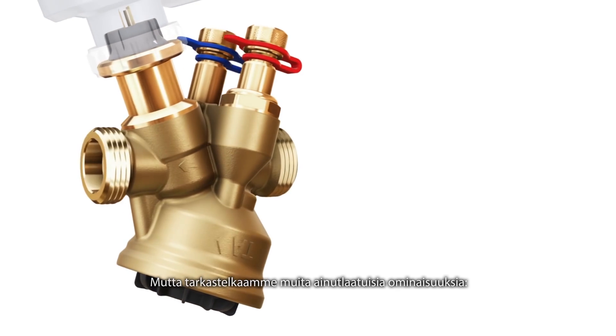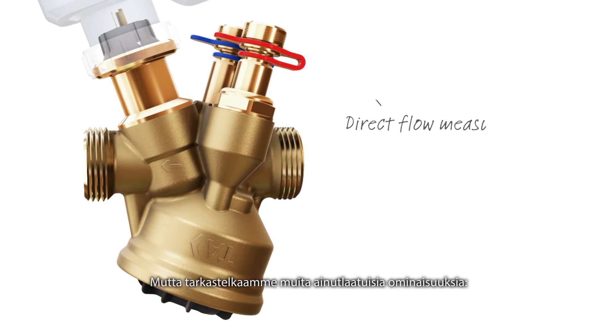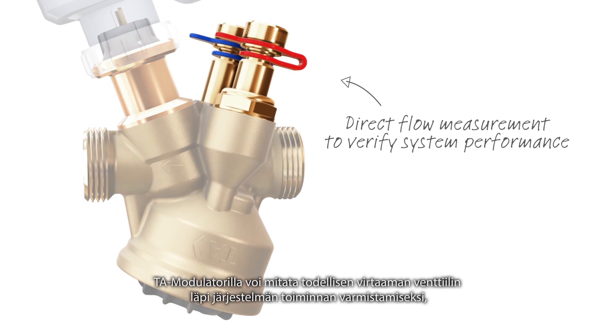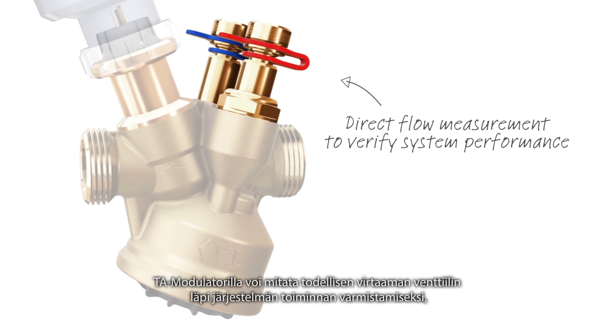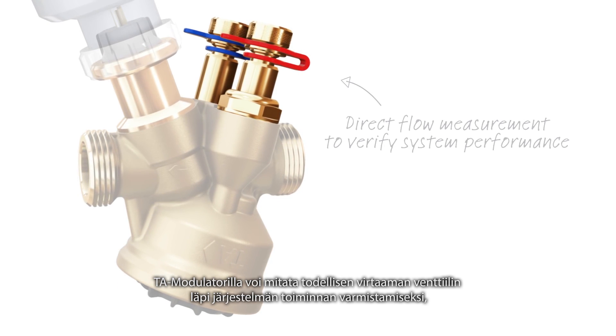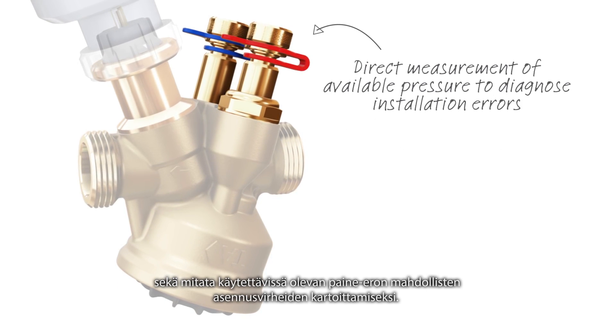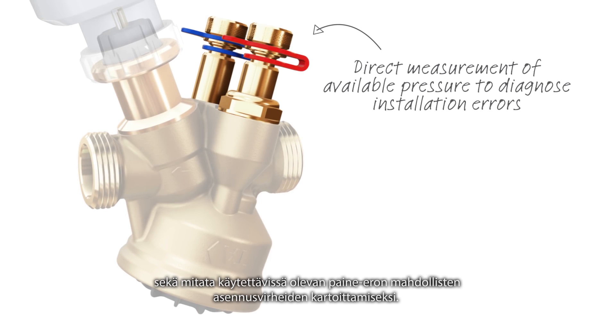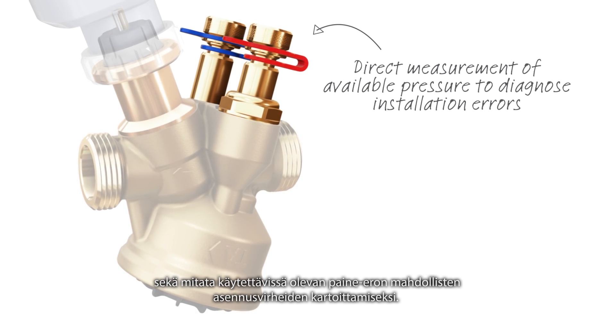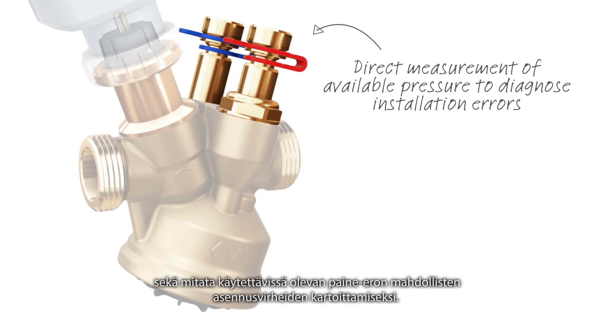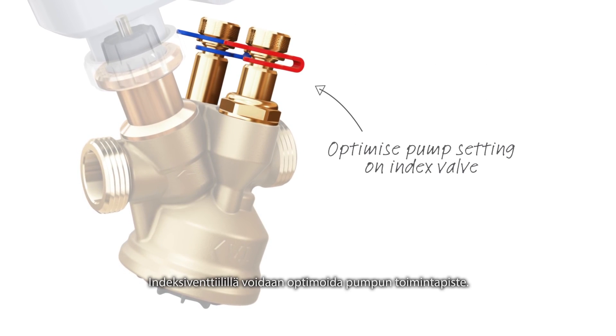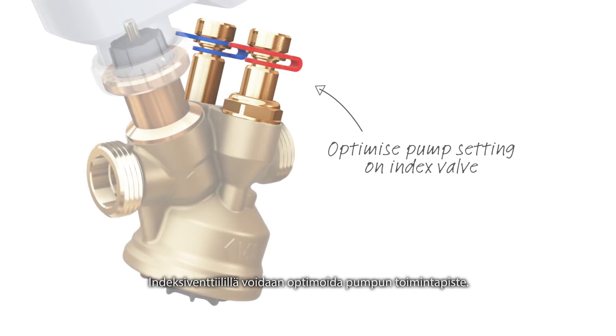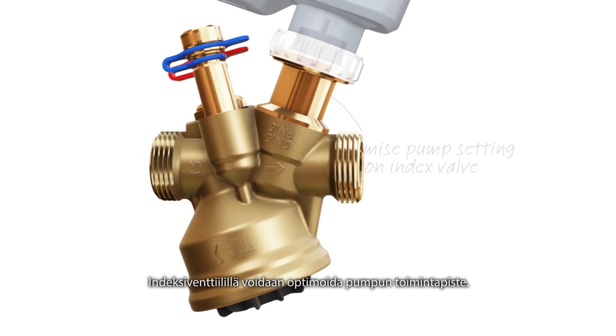With TA modulator, you can measure the true flow through the valve to verify the system performance, as well as measure the available differential pressure to diagnose possible installation errors. On the index valve, you can optimize pump setting.